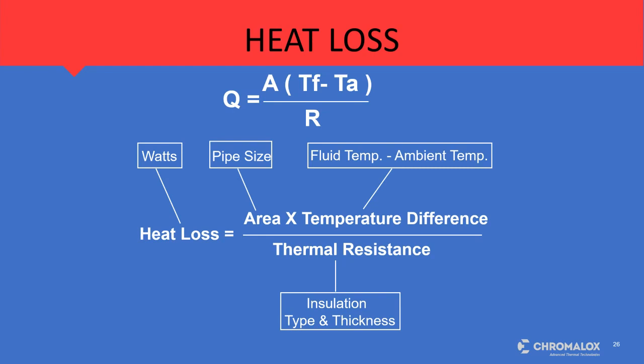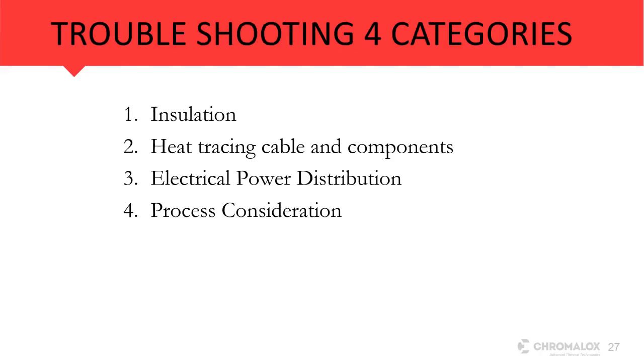And that heat loss comes from your basic thermodynamics equation, right? Heat loss equals area times the temperature difference divided by thermal resistance, which in this case is our pipe size, the fluid temperature minus ambient, divided by our insulation types and thicknesses. That equation comes out of our Chromotrace calculations, so those are done automatically today. Years ago, you had to go into the graphs and calculate those heat losses. So that's a basic overview of heat tracing. I just want to make sure everyone understands that. So let's look at four key categories or systems that you need to look at whenever you're going to do some troubleshooting in heat tracing.